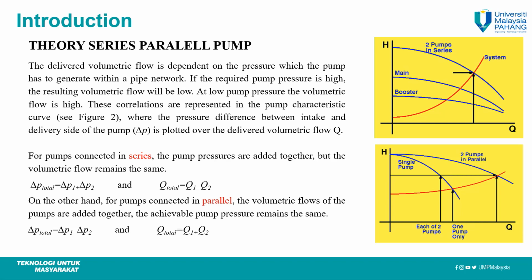When we talk about parallel pumps, in most parallel operations, a bank of pumps is combined in order to handle high fluctuations of flow in a common system. In such arrangements, all the pumps take their suction from a common source and then discharge into a common header. Each pump operates at the same head, so the pressure remains the same, but they share the flow rate with other pumps and help increase the flow rate.